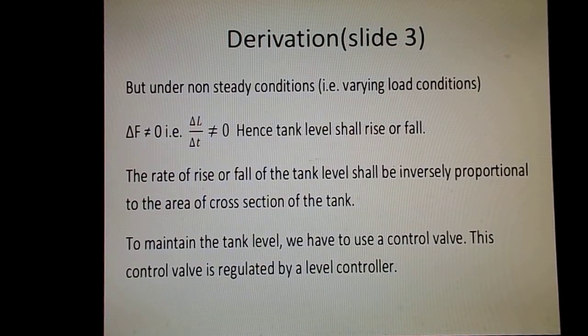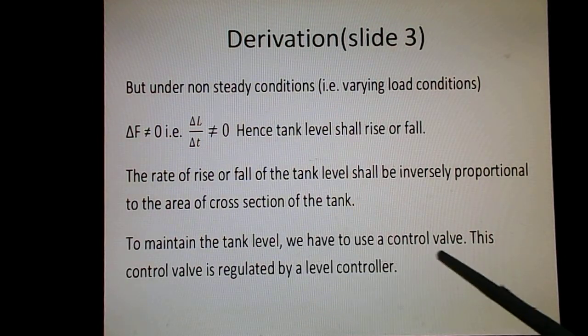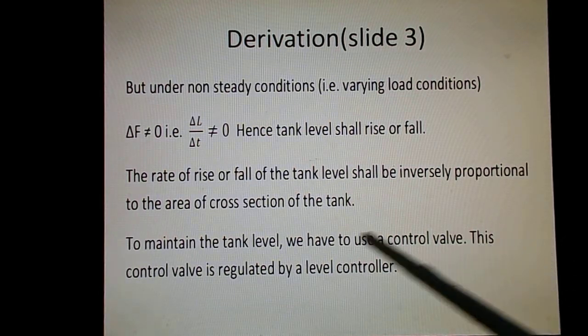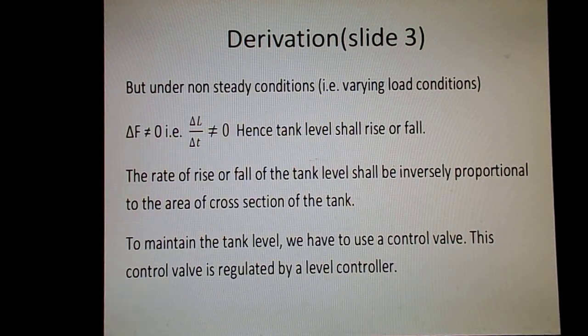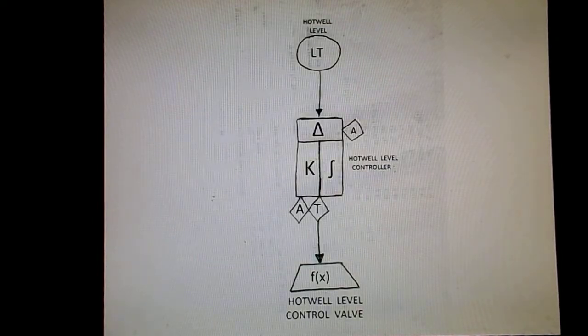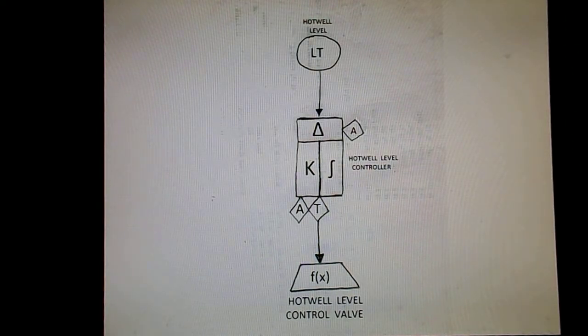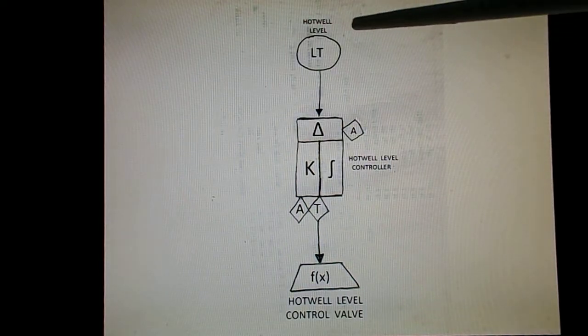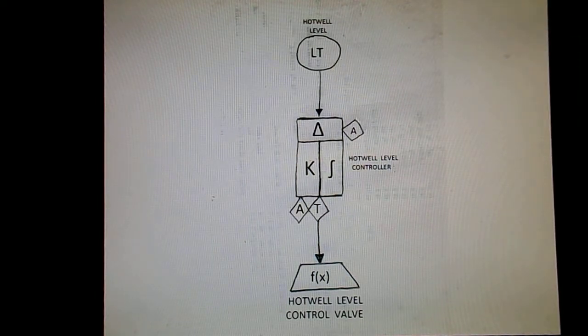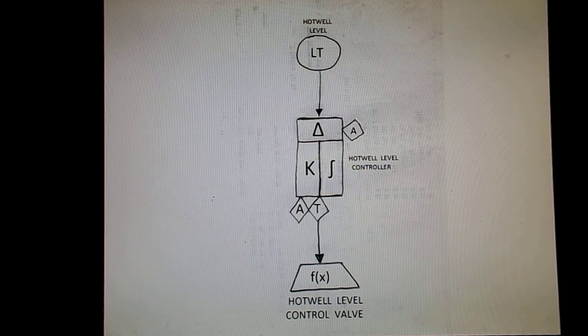From this relationship, we conclude that to maintain the tank level, a control valve is needed, regulated by a level controller. A typical level controller scheme is shown here: a level transmitter sends its output to a PID controller, and the PID controller output drives the control valve.